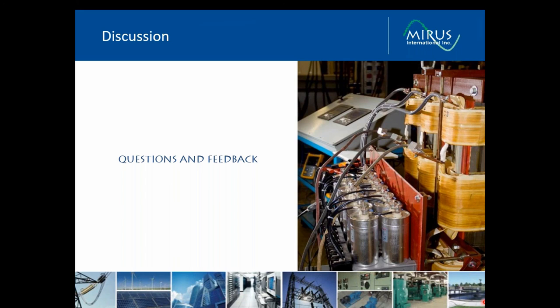But sometimes when you have parallel generators, I don't know if there are parallel generators in this situation, but sometimes you'll get circulating currents between the generators. These are typically at three times the frequency of the fundamental. I don't like to refer to it as a harmonic because it's actually not a distorted current that's present. It's actual three times the frequency current that's circulating. That is likely what's causing your circuit breaker to trip. We can definitely take that offline if you want some further discussions. We do have devices that can limit circulating currents if that is your problem. It's a different device than I presented today, but we do have a solution available.